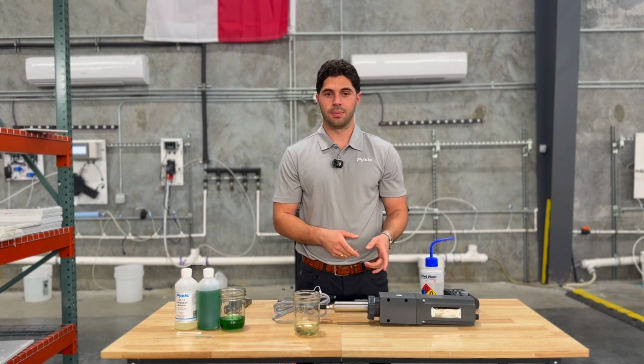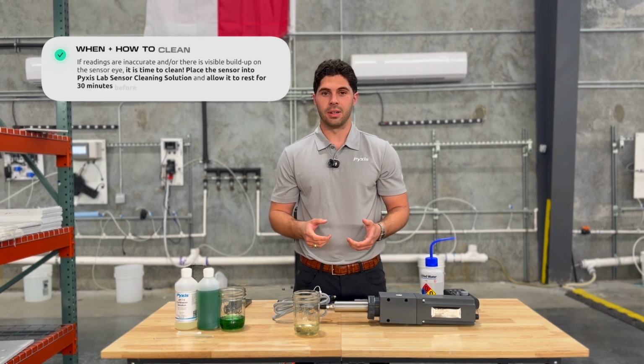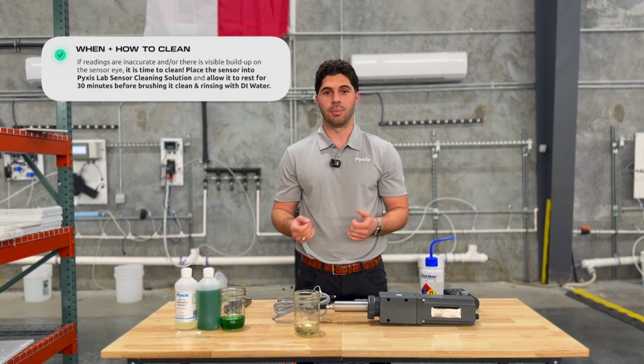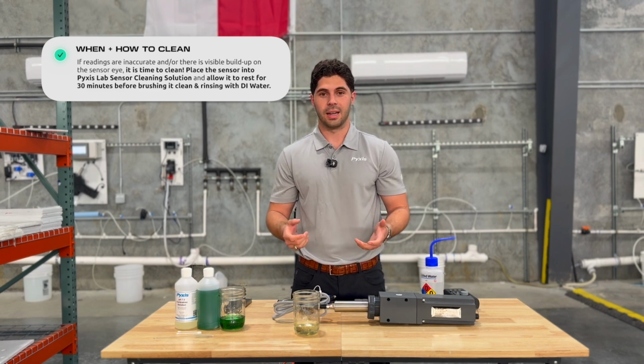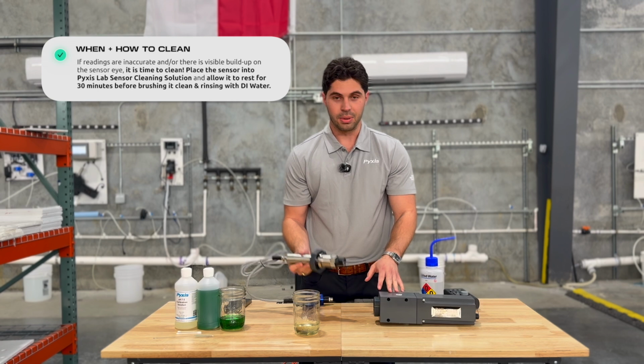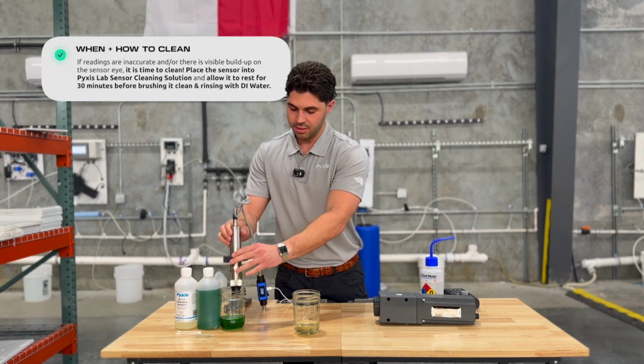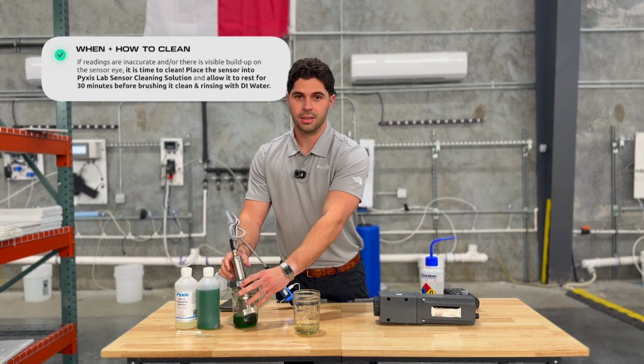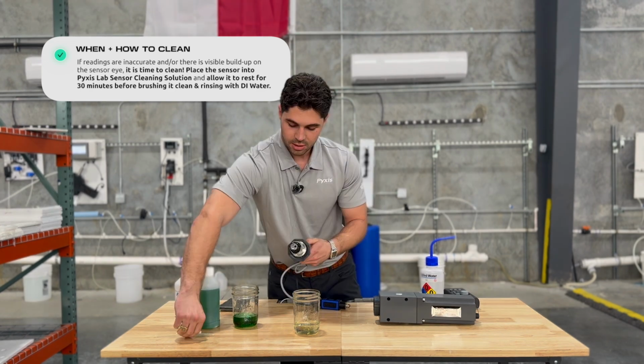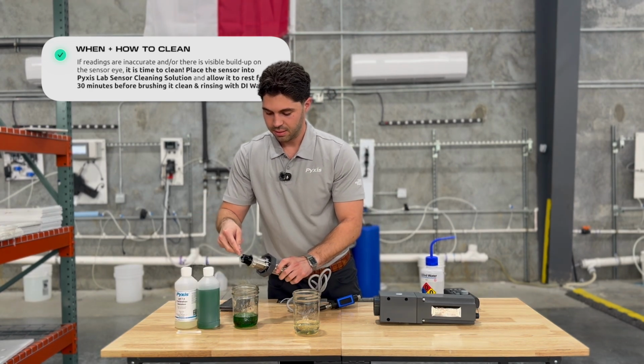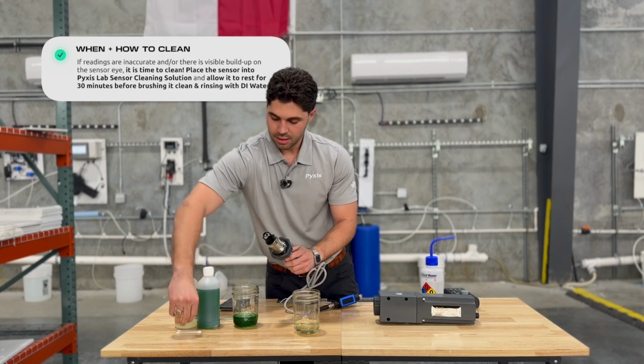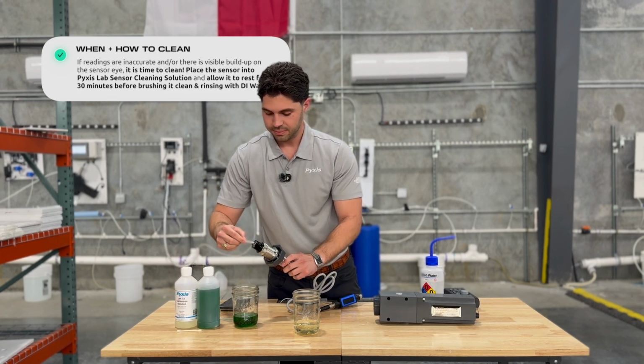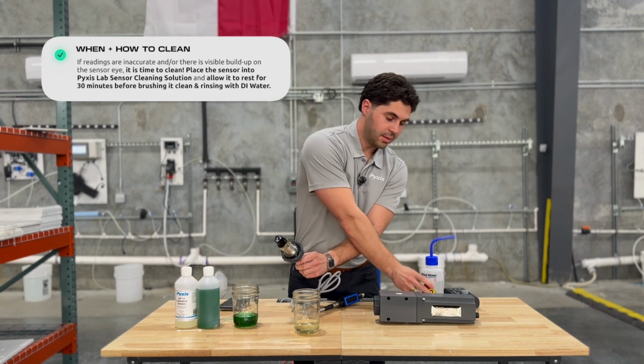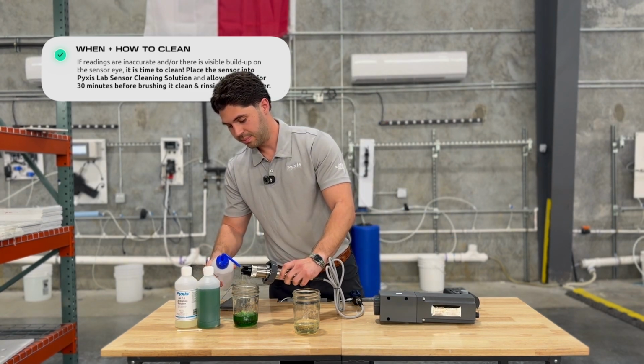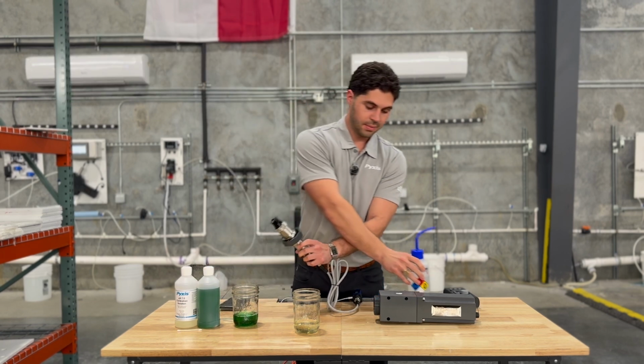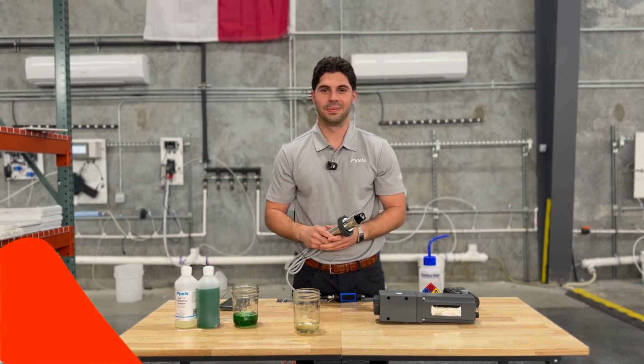If after you place the sensor back in the system, you're still getting inaccurate readings, or before you calibrate, you notice large deposits or buildup on the sensor head, it's time to clean it. To do so, you're going to place the sensor in our cleaning solution for about 30 minutes. Once you've let it sit, take it out, scrub it with the brush, clean it with the felt pads, and rinse with DI water. You should be good to go.